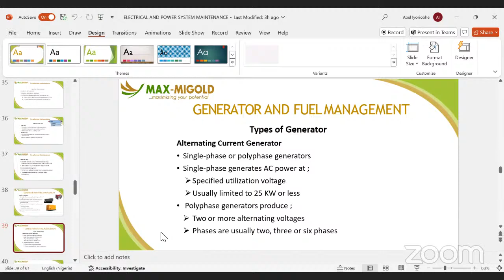We have the single phase generator, like the one you have at home. Like I told you, when you are carrying out your load analysis, you have to know the type of load that you have in your building, so that you will not go and recommend a 3-phase instead of a single phase, or vice versa. You have to know the type of load in your facility. This is what makes you different from every other maintenance person. As a facility person, you should know the type of load you have in your facility, so that the cost and your function can be met.